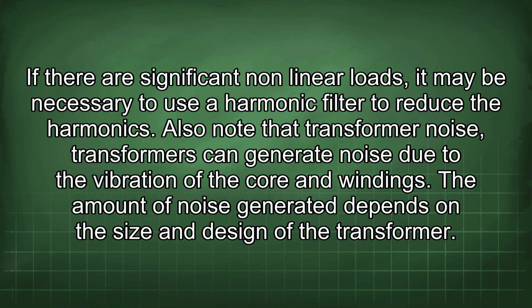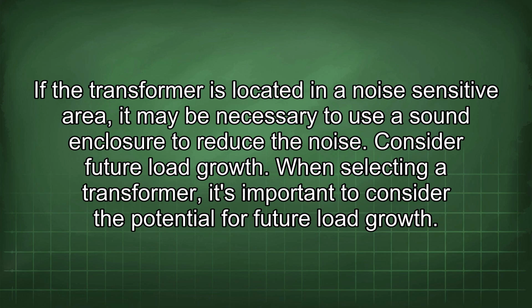Also note that transformers can generate noise due to the vibration of the core and windings. The amount of noise generated depends on the size and design of the transformer. If the transformer is located in a noise-sensitive area, it may be necessary to use a sound enclosure to reduce the noise. Consider future load growth.